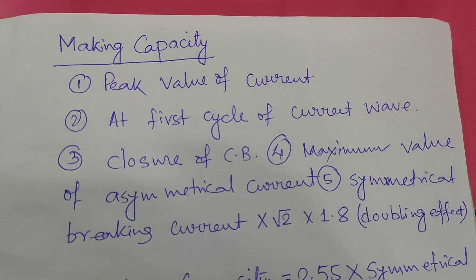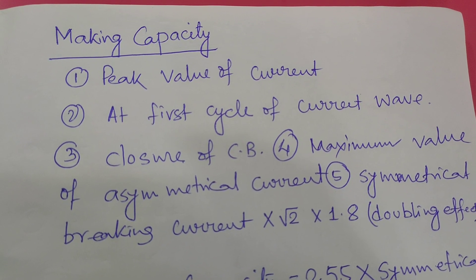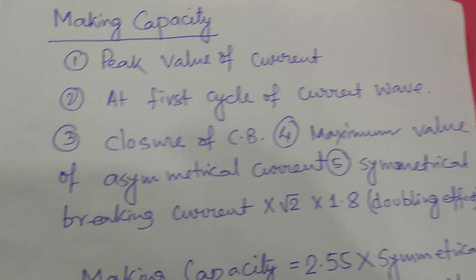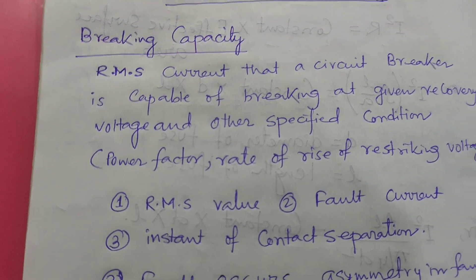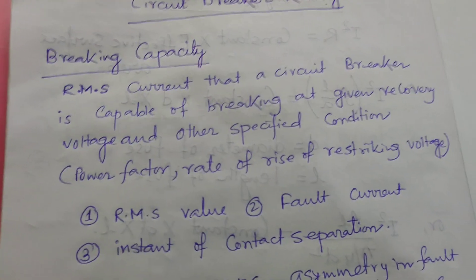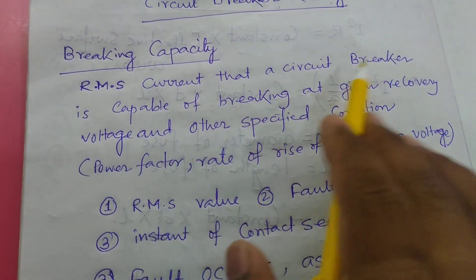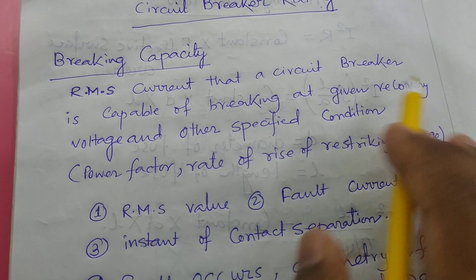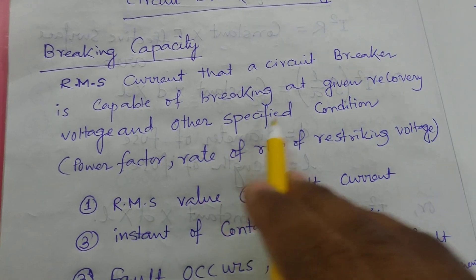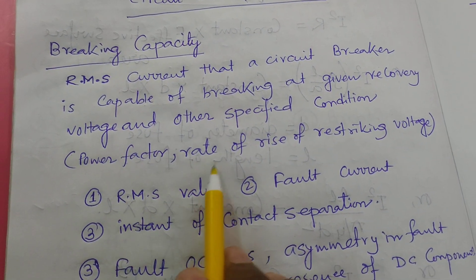So Closing and Making is the same concept. It has a capacity — we will discuss the Making Capacity of the Circuit Breaker. Now let's start about the Breaking Capacity of the Circuit Breaker. It is the RMS current that a Circuit Breaker is capable of breaking at a given recovery voltage and under other specified conditions such as power factor.